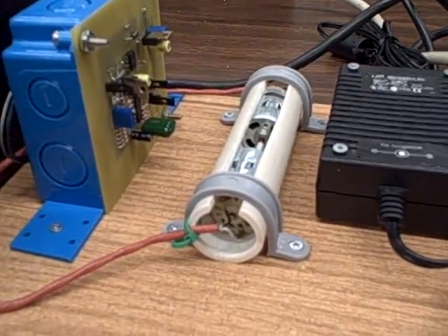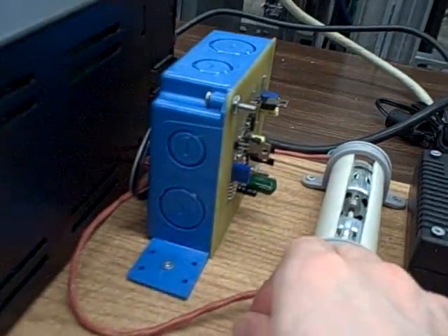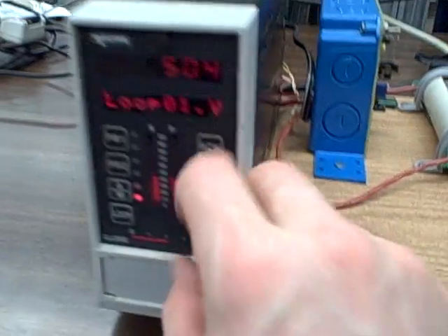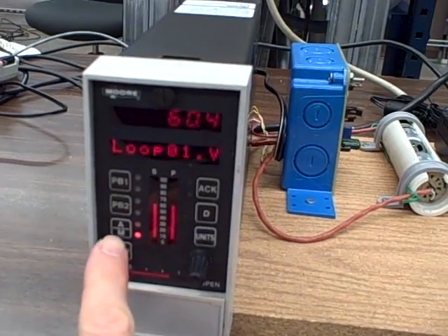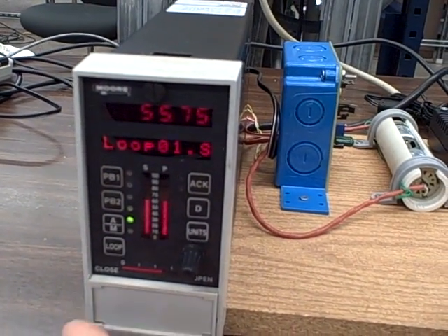All we need to do, however, is go over here and reverse the action of our variable speed motor drive once again, so it is now direct acting. And when we do this, I'll decrease my output so we're not surprised by a runaway motor. Plug in our load jumper, and now we should have a properly controlling system. Negative feedback. I'll throw it into automatic mode, and here we go.